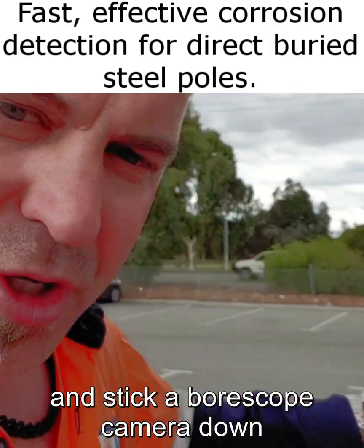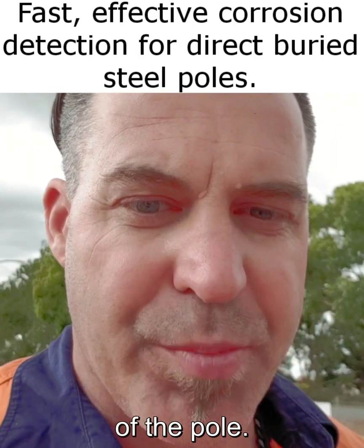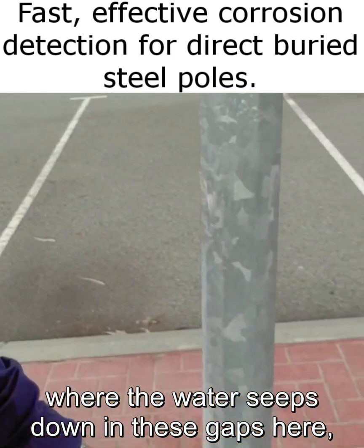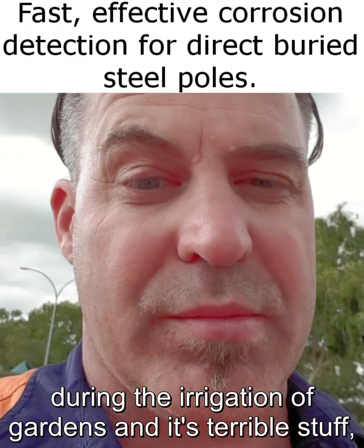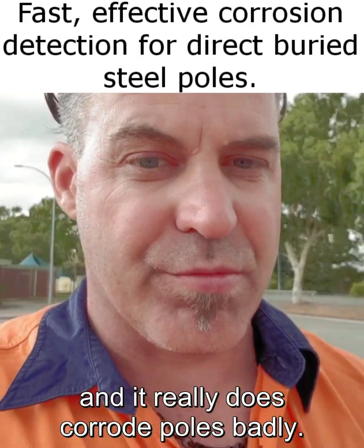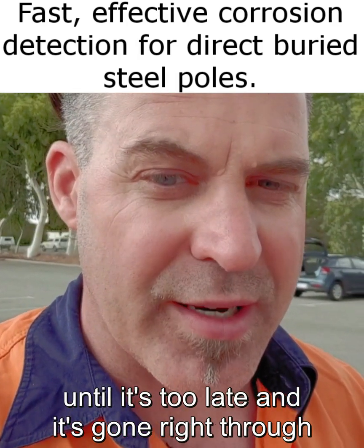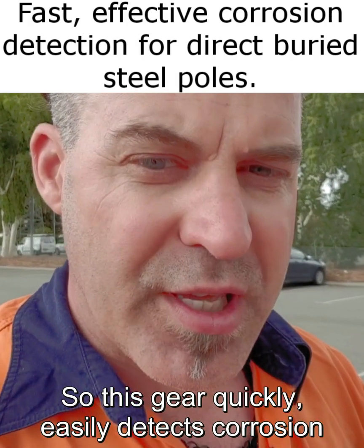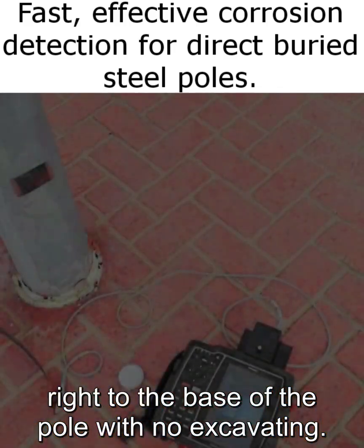Some other companies take the inspection panel off and stick a borescope camera down to look for corrosion, but that's only going to show you the corrosion on the inside of the pole. Most of the corrosion is from the outside, where water seeps down in these gaps. There's a lot of bore water from garden irrigation which really does corrode poles badly. You're never going to see it from the inside until it's too late — until it's gone right through the wall thickness and the pole is about to fall over. This gear quickly and easily detects corrosion right to the base of the pole with no excavating.